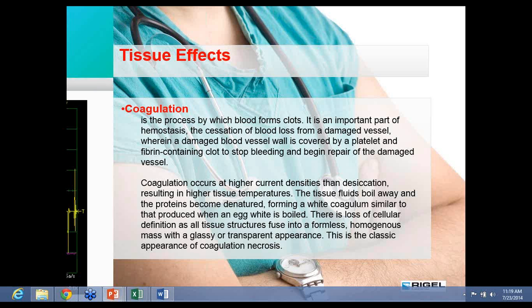Okay. This coagulation is completely different. It's a high current density, much higher current density than desiccation, and that's achieved by the slowly rising amplitude of the RF energy. The tissue actually boils, and proteins become denatured, forming a white coagulum similar to that when an egg white is boiled. So you know what happens with a hard-boiled egg, it's no longer runny, it becomes a firm jello-like substance. That's what happens during coagulation. The cellular definition goes away. It's formless. It's no longer unique, homogeneous. This is what's known as coagulation necrosis.